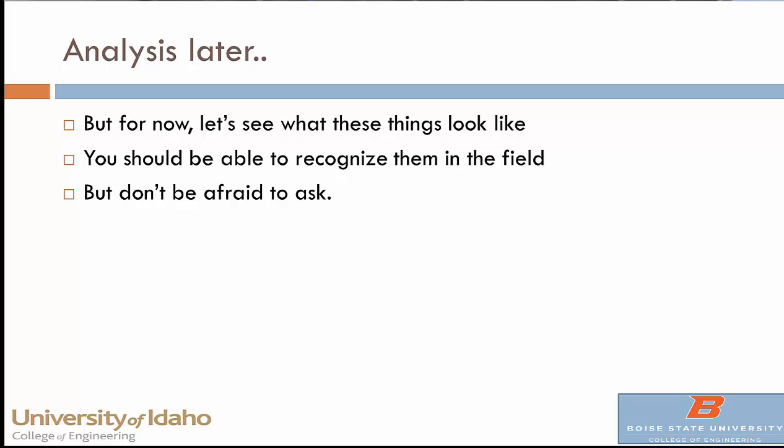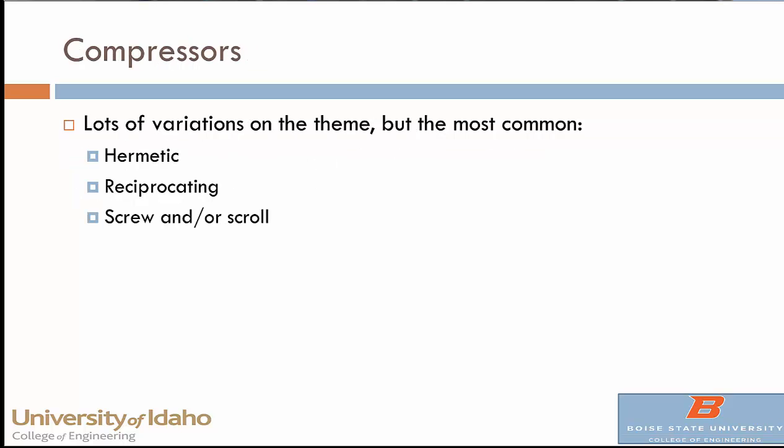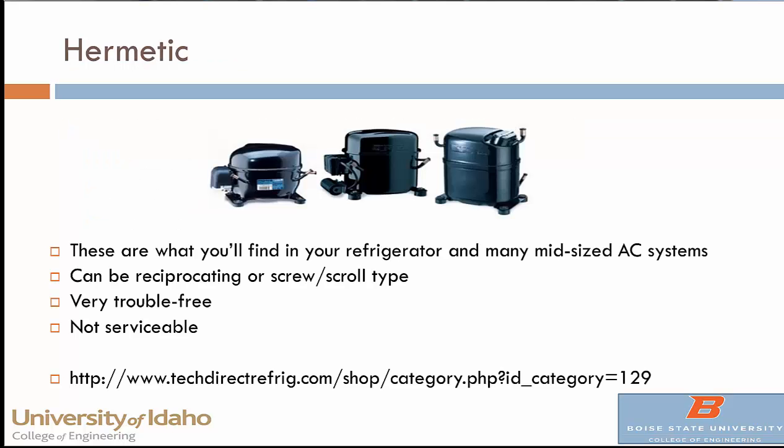Let's look at what these things look like — so far they've been blocks on generic diagrams, so let's look at some photographs. Starting with compressors: the hermetically sealed type is what you'll find in the back of your refrigerator or inside your air conditioner — a black cylinder with pipes sticking out. It contains oil and handles the compression all in one spot. Low-pressure, low-temperature vapor goes in; high-temperature, high-pressure vapor comes out. These are designed to last the lifetime of the device — 20, 30, or 40 years. The downside is they're not serviceable; when they go bad, you pull them out and put a new one in.